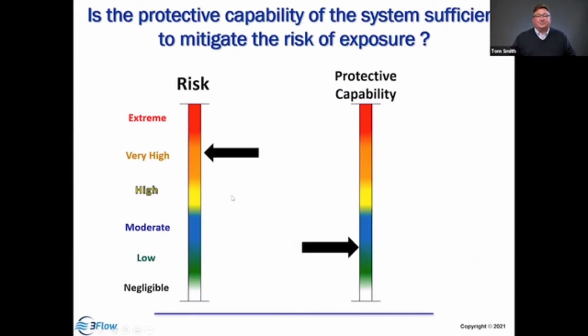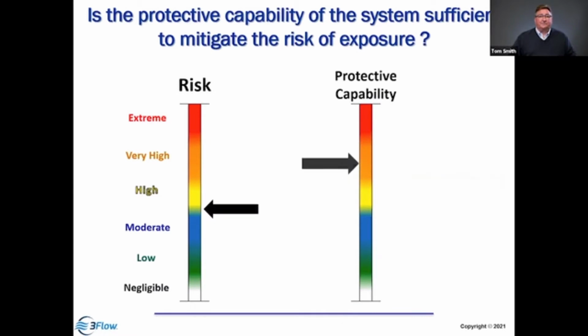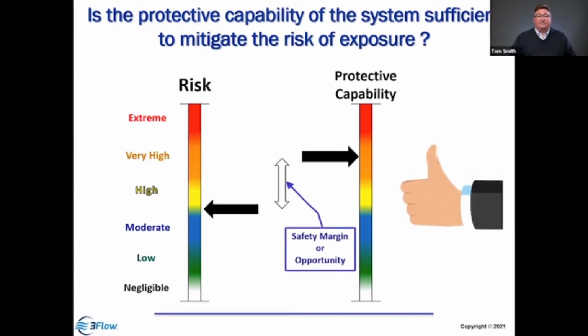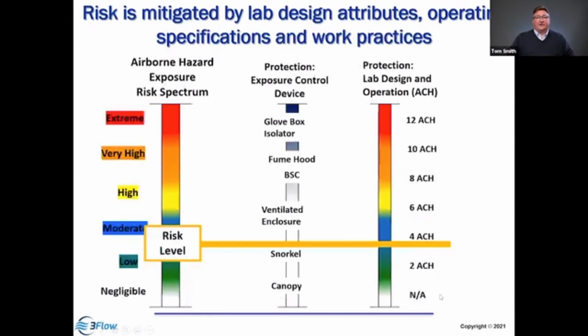And we want to match that to the protective capability of the space. If the risk level is very high, but the protective capability is low, that's a big difference, and that would be bad, right? We want to have the protective capability greater than the level of risk, so that when we look at that difference, that is the margin of safety, or it's also an opportunity. So if the protective capability greatly exceeds the level of risk, maybe we can right size that system and save some energy, right? But we need to know the risk and the protective capability required in order to ensure that we're making the appropriate change.